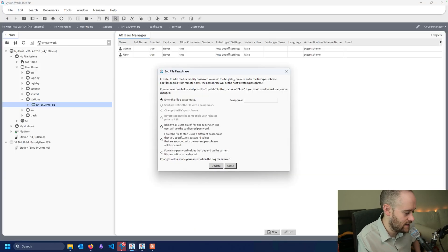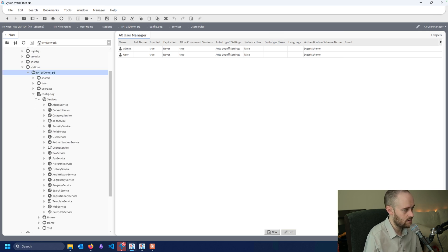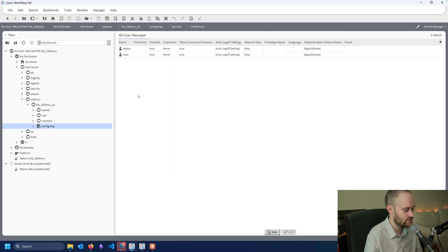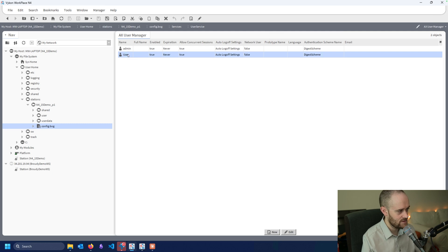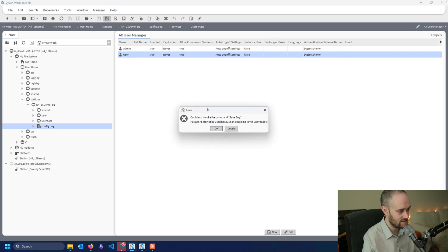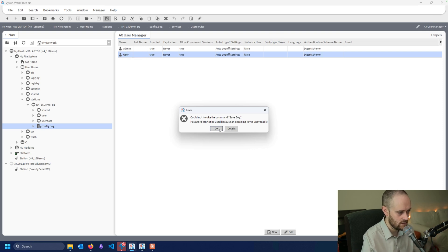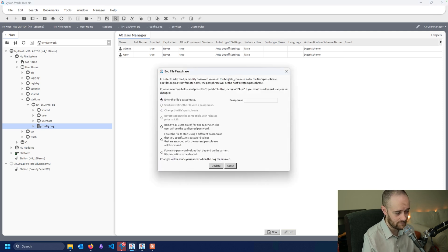We're in Niagara now and I have opened up a bog file. We're going into our file system, then our stations, opening up a station and opening up the bog file in that station. Then we come into our user service. In this case, I've already added in a user — which is actually an admin user. I put in that admin user and I go to do a save as I normally would, and I can't because I don't have an encoding key or passphrase. So I hit OK and go to our unlock button at the top.